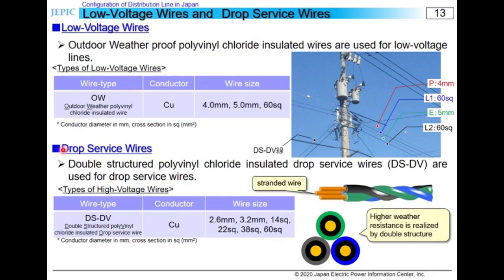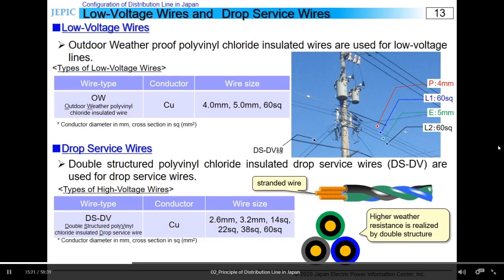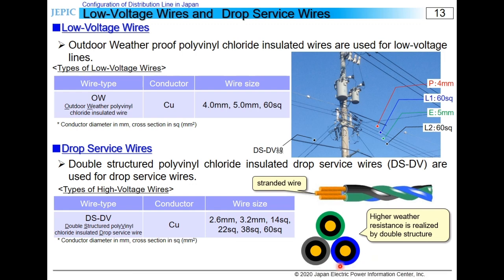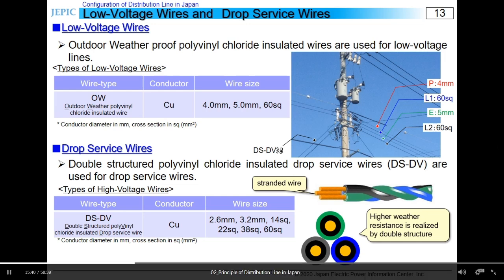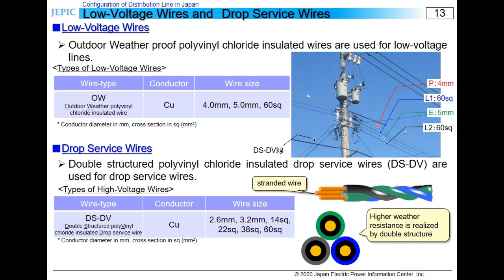As for drop service wires, the stranded wires like this figure are used, called DSDV wire. There are two conductor type and three conductor type. DS represents double structure, which has two layers in its insulator. As you can see in the cross-section illustration, the inner layer is black, which has a higher weather resistance, and the outer layer is colored black, blue, and green to see the phase. In the past, its insulator had consisted of a single layer with color, but compared with black, color insulation layers have lower weather resistance, so they deteriorated more easily, resulting in short circuit and disconnection. So this kind of wire was developed and has been installed.